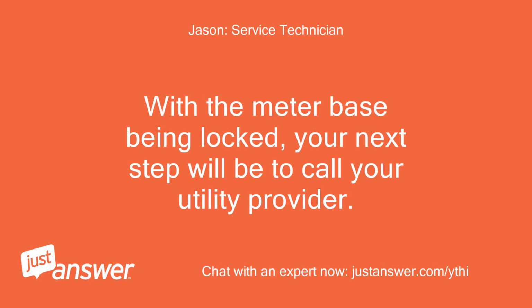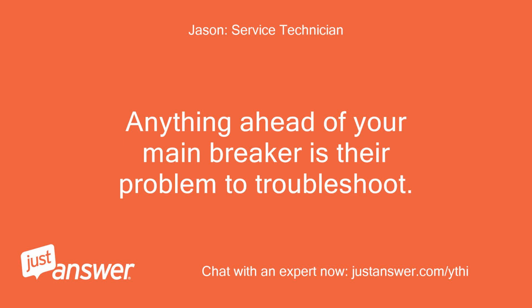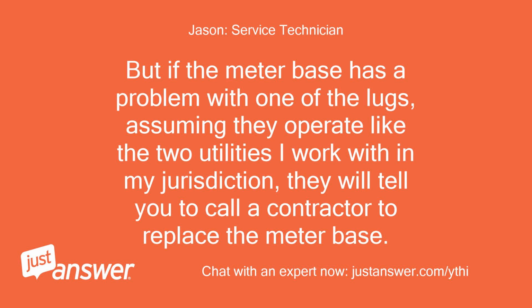With the meter base being locked, your next step will be to call your utility provider. Anything ahead of your main breaker is their problem to troubleshoot. But if the meter base has a problem with one of the lugs, assuming they operate like the 2 utilities I work with in my jurisdiction, they will tell you to call a contractor to replace the meter base.